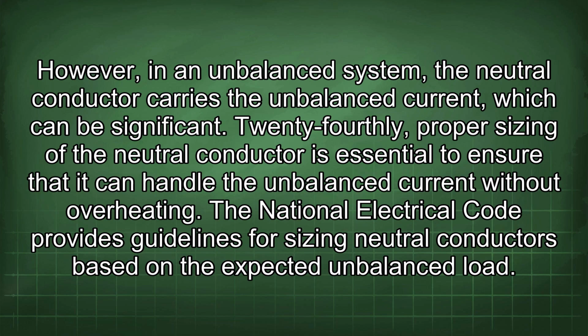24thly, proper sizing of the neutral conductor is essential to ensure that it can handle the unbalanced current without overheating. The National Electrical Code provides guidelines for sizing neutral conductors based on the expected unbalanced load.